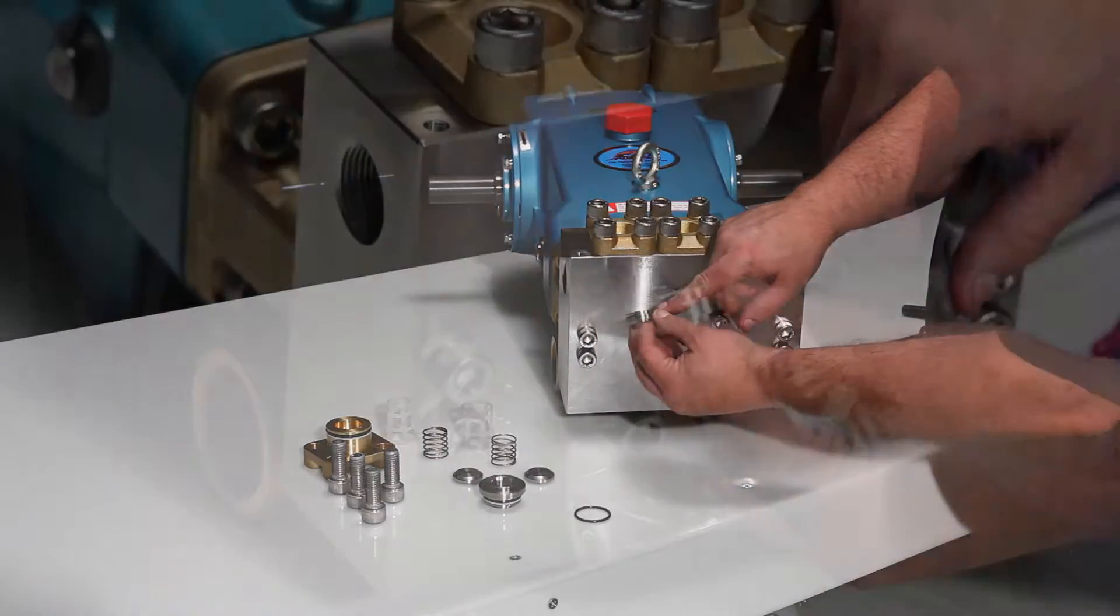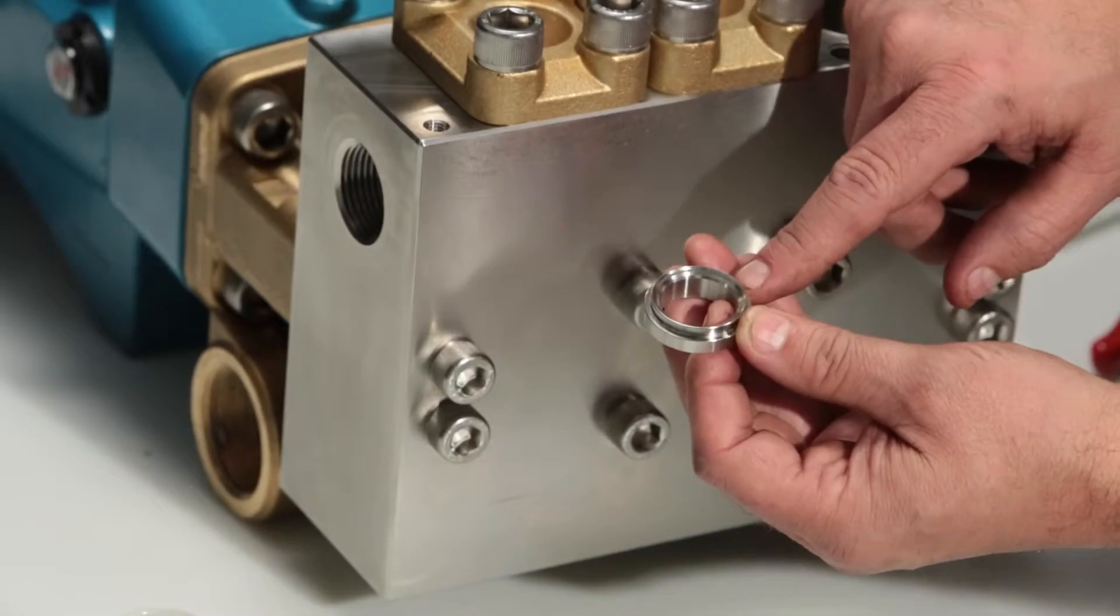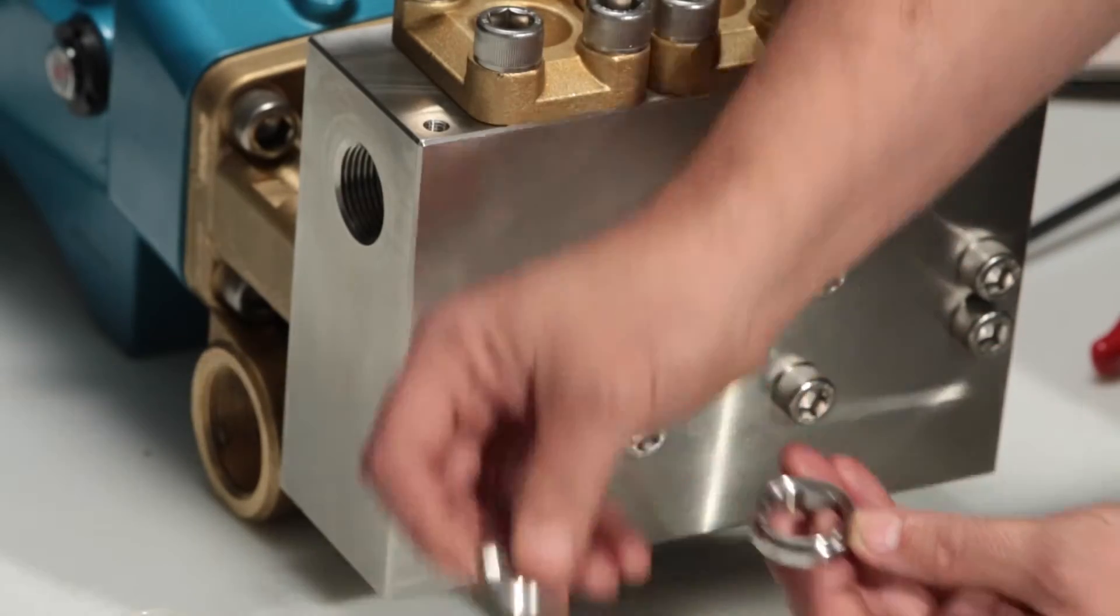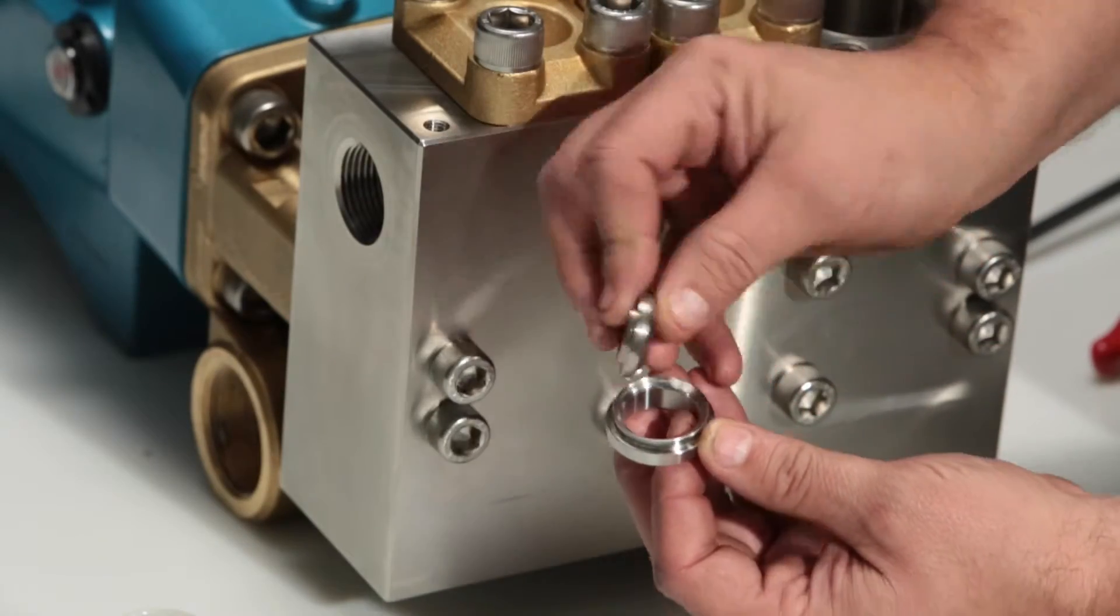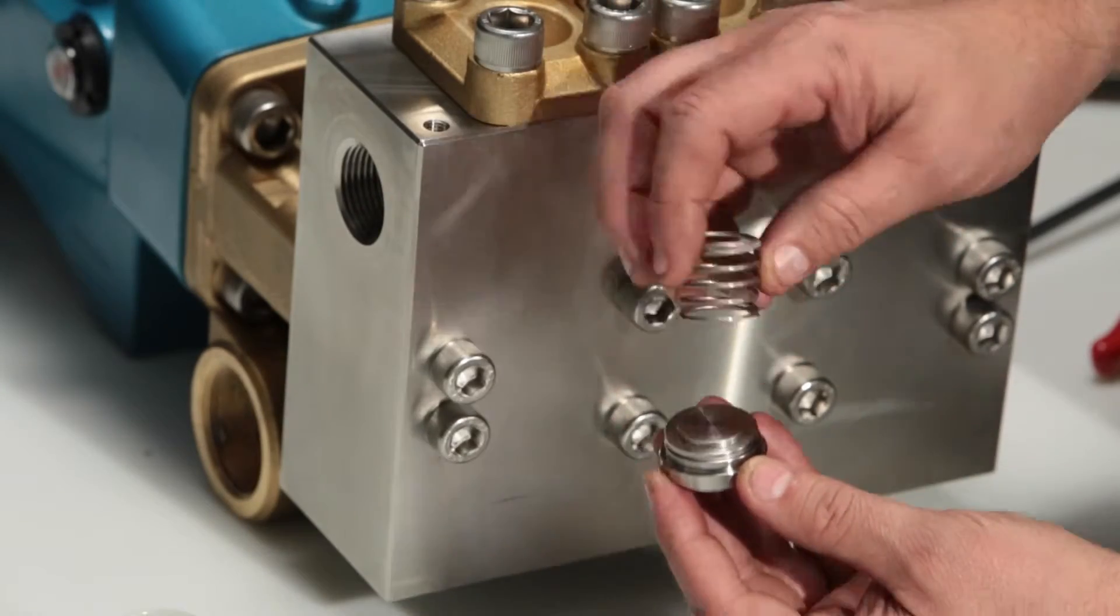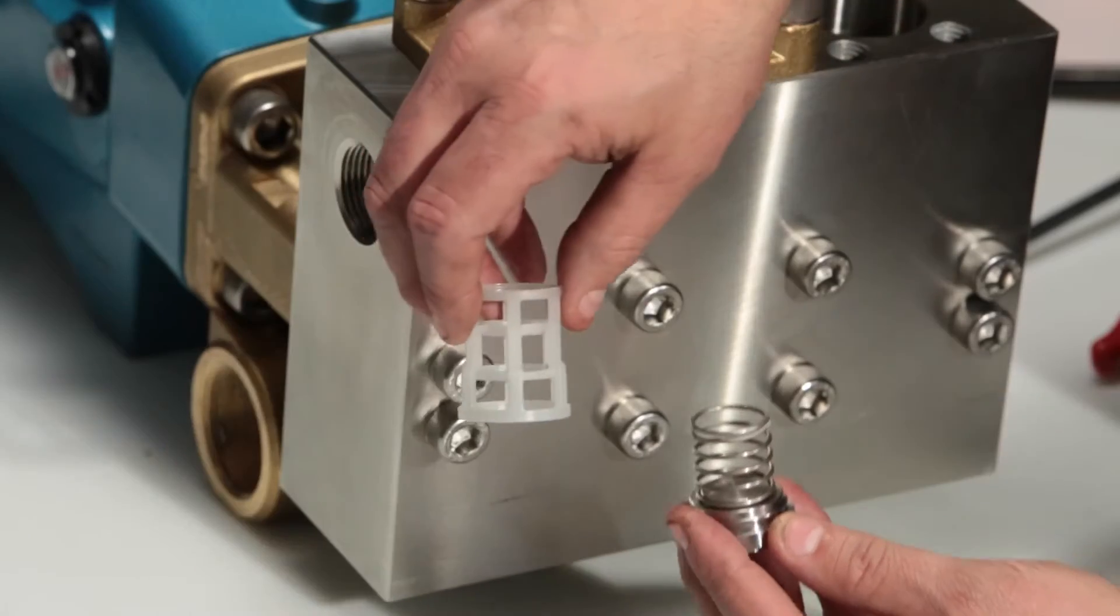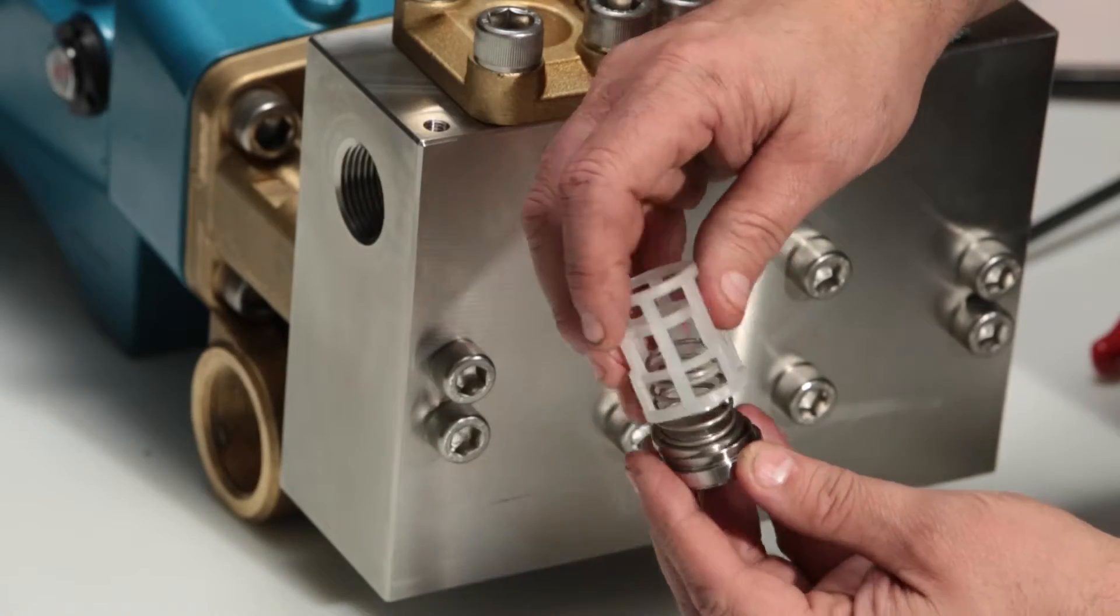To reassemble the valve, take the inlet valve seat, then the valve, then spring. The inlet valve retainer has only one step, opposed to the discharge, which has two.